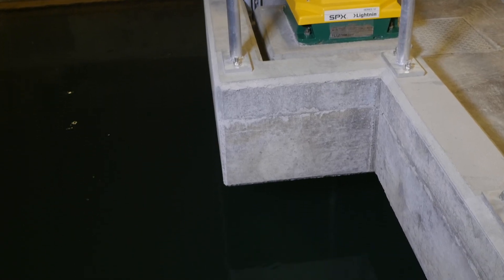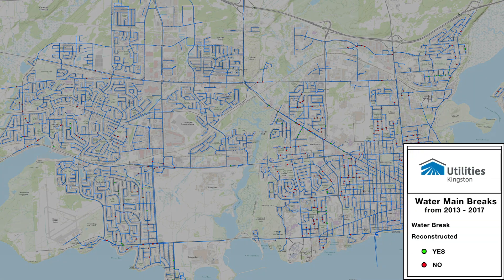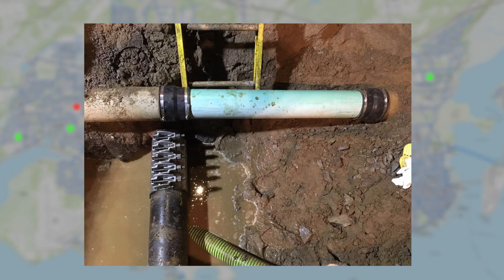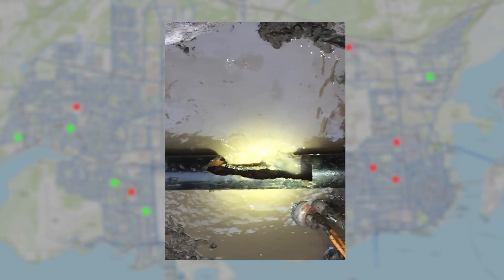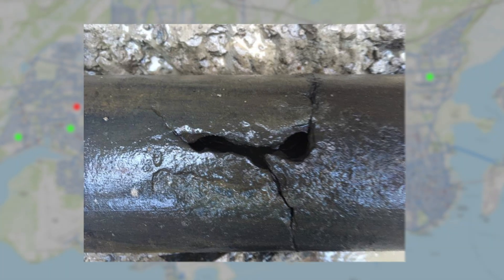We look at how much water we pump out of our central water treatment plant and how much we're metering. We weren't calculating that within our own operations. Water is used to flush the mains, to measure the flows at our fire hydrants so we can put the ratings on them and colour-code them — that amount of water was not necessarily being accounted for; it's not revenue. Once we did that, we started looking at where do we have leaks, where do we have losses, and so now we've got the true non-revenue water — the stuff that comes out of the plant and just disappears. Over the last three years, we were able to identify over 440 leaks, and by fixing those, we were able to save 2 million metres cubed.